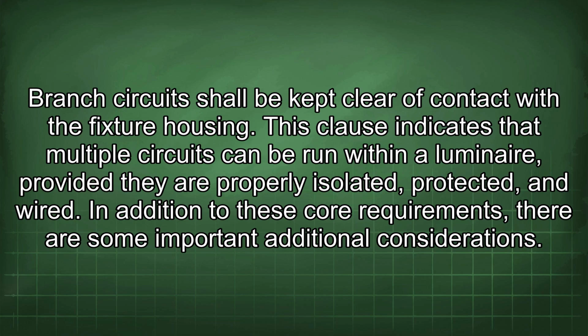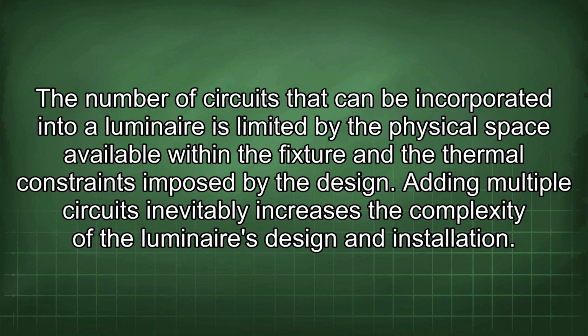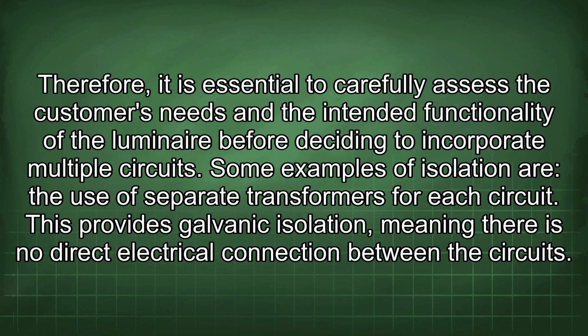In addition to these core requirements, there are some important additional considerations. The number of circuits that can be incorporated into a luminaire is limited by the physical space available within the fixture and the thermal constraints imposed by the design. Adding multiple circuits inevitably increases the complexity of the luminaire's design and installation. Therefore, it is essential to carefully assess the customer's needs and the intended functionality of the luminaire before deciding to incorporate multiple circuits. Some examples of isolation are the use of separate transformers for each circuit.